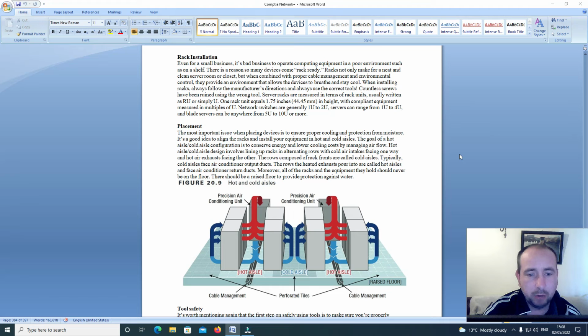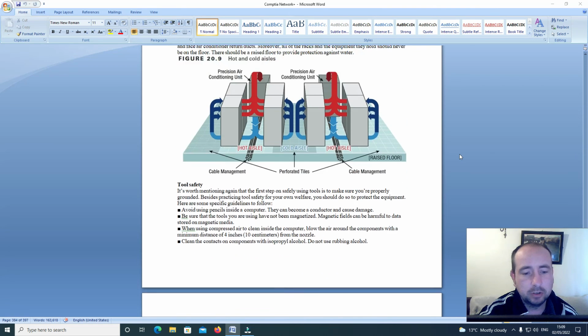It's a good idea to align the racks and install your equipment in hot and cold aisles. The goal of a hot aisle cold aisle configuration is to conserve energy and lower cooling costs by managing airflow. Hot aisle cold aisle design involves lining up racks in alternating rows with cold air intakes facing one way and hot air exhausts facing the other. The rows composed of rack fronts are called cold aisles. Typically, cold aisles face air conditioner output ducts. The rows the heated exhausts pour into are called hot aisles and face air conditioner return ducts. Moreover, all of the racks and the equipment they hold should never be on the floor. They should be on a raised floor to provide protection against water.